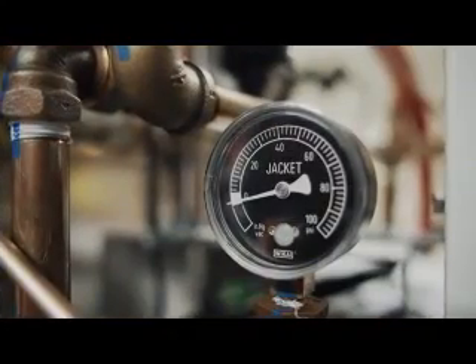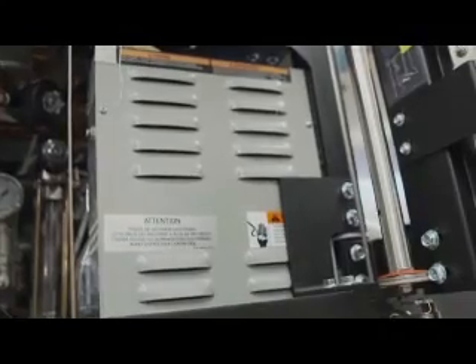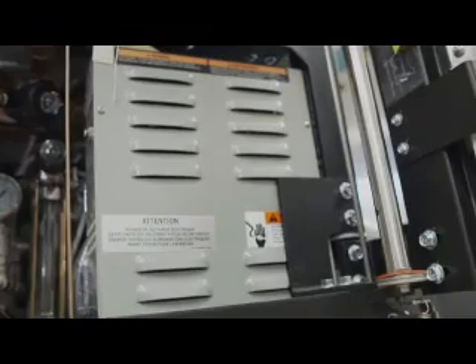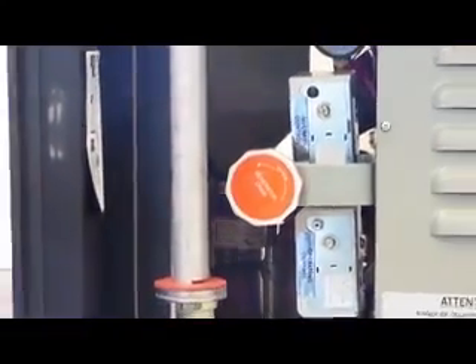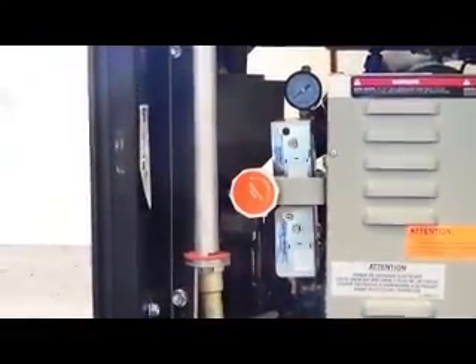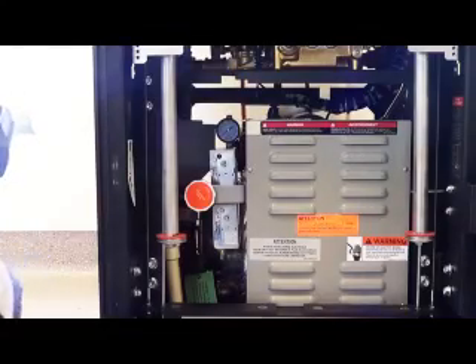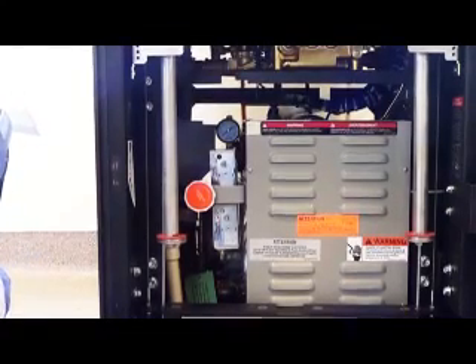For sterilizers equipped with an integral electric steam generator, there may be a mechanism for automatically flushing the generator daily. If your sterilizer is set up to be flushed manually, there will be a valve associated with flushing the steam generator. Instructions for flushing the generator are provided later in this video. Please consult your operator manual in conjunction with this video for instructions.